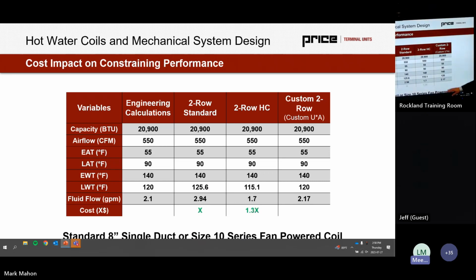Cost. A standard to a high capacity coil from Price, just on the coil itself, not on the total single duct or fan powered box, is about a 30% increase in cost. Anyone want to guess what the cost increase is from a standard 2-row to a fully custom 2-row water coil? 50% more. Anyone else? It is higher than 50% more. I'll keep us going in the right direction. 4 times more? It's more than 4 times more. It's more than 5 times more as well. We're getting close.